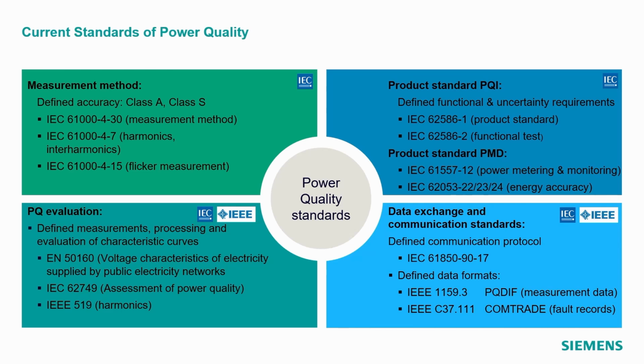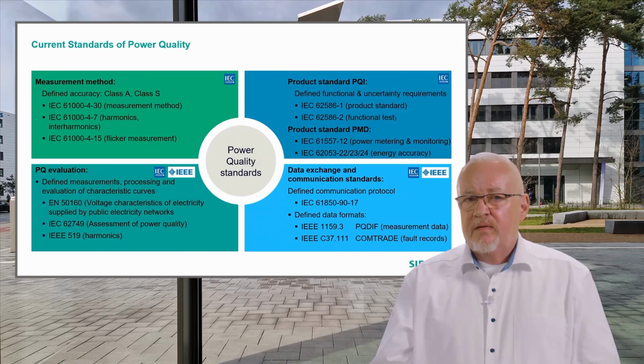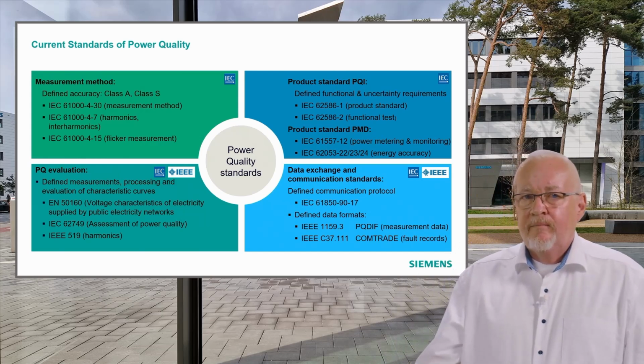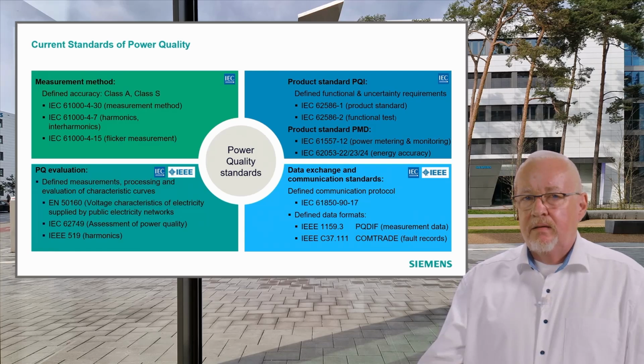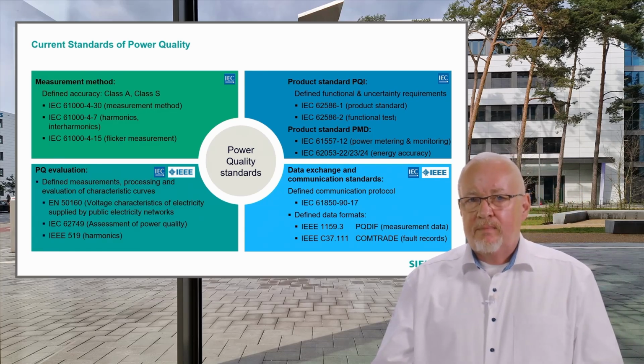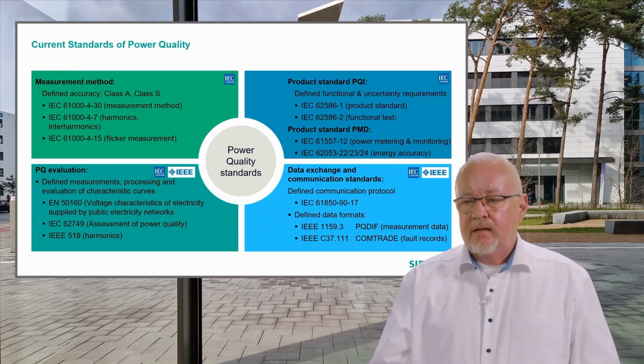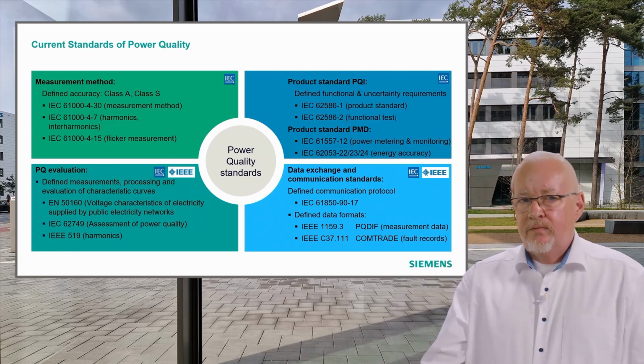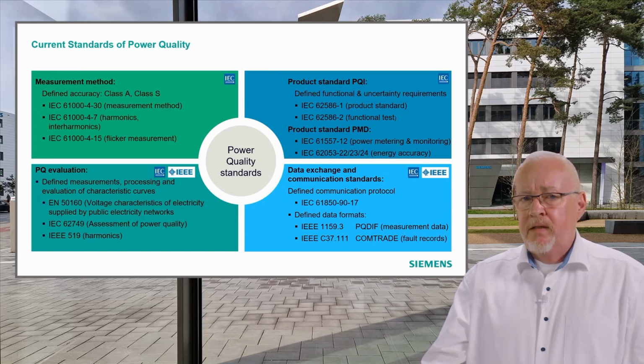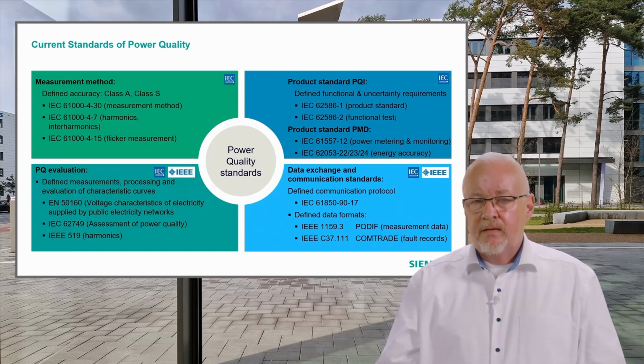There's also an IEC standard available meanwhile with edition 2, assessment for power quality. It's a little bit different from EN 50160, and one is developed in Cenelec and another one is developed by IEC. I don't see a fast standard together between Cenelec and IEC. It's not planned to have this standard in a short future. There are also some other standards which are dealing with power quality evaluation, especially inside industrial installations, demand-side power quality guideline for operators in industrial installations, and compatibility levels in industrial plants for low-frequency conducted disturbances.